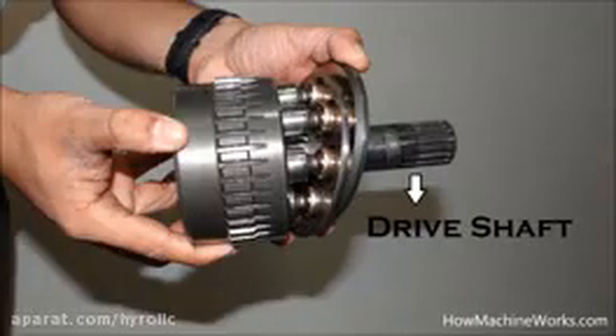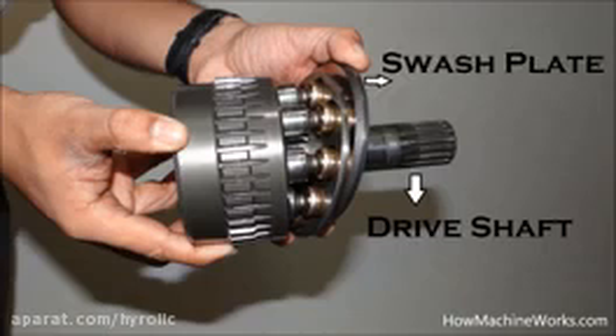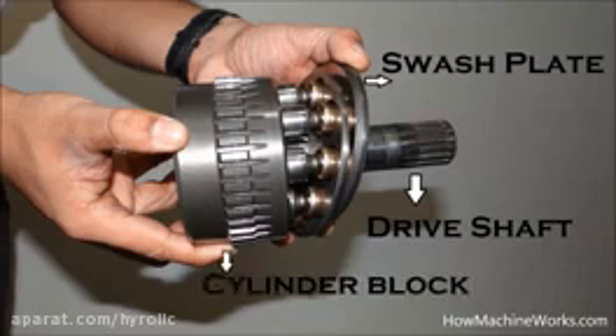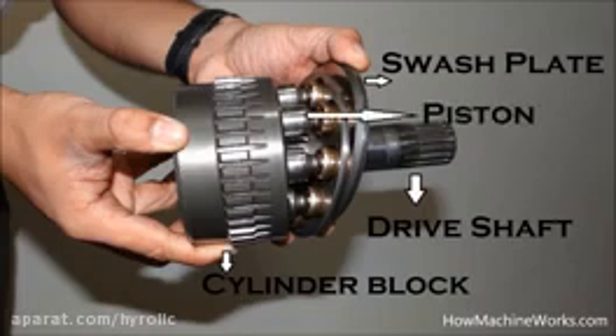That's the drive shaft, which is a part of the cylinder itself. The drive shaft gives drive towards the cylinder, and that's the swash plate, which I told the pistons are resting and sliding over. The swash plate angle changes, the flow varies. That's our cylinder block in which we have the pistons arranged, and as the cylinder block rotates, the pistons slide over and axially reciprocate. That's the pistons over there. We have many pistons arranged inside a particular cylinder block.